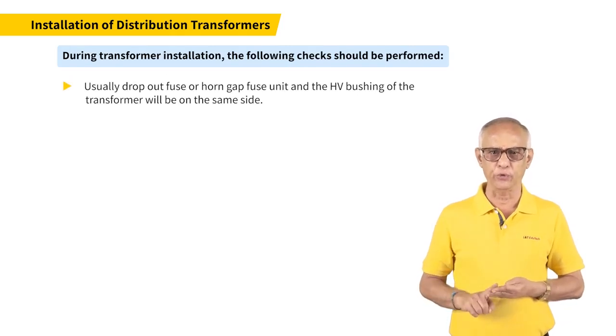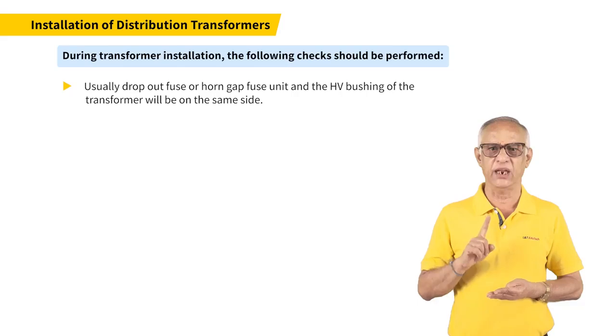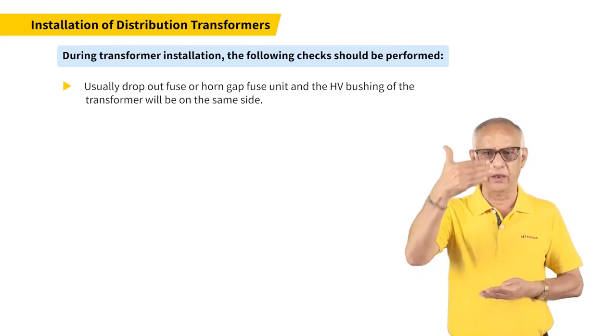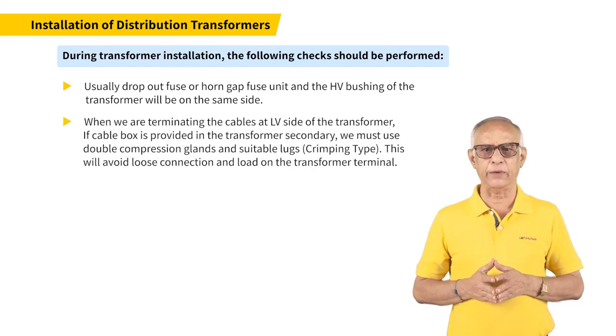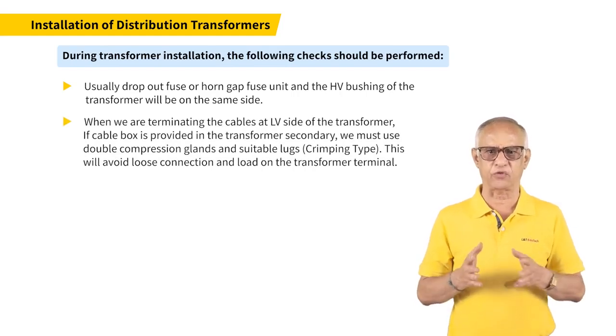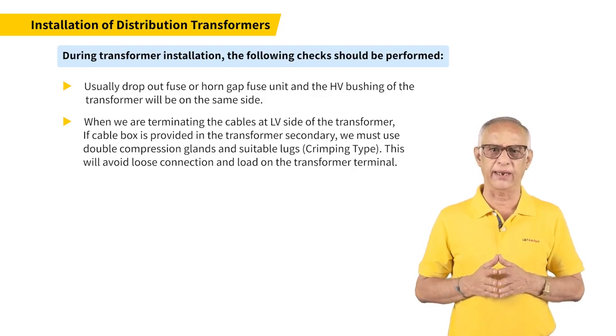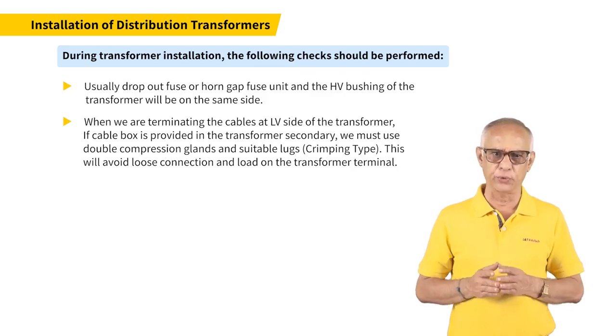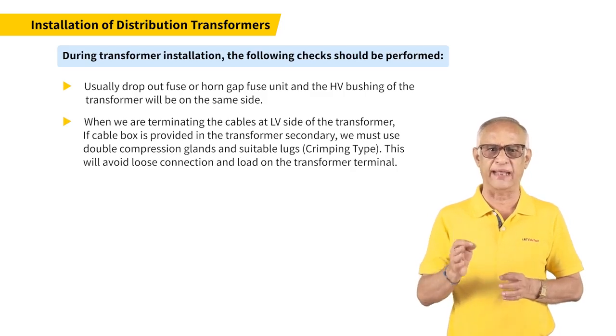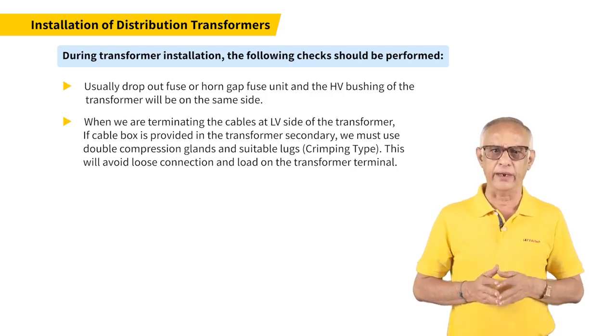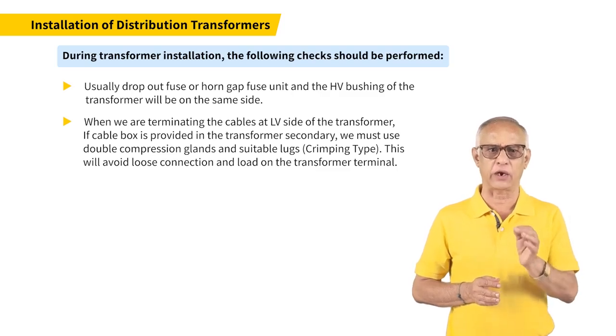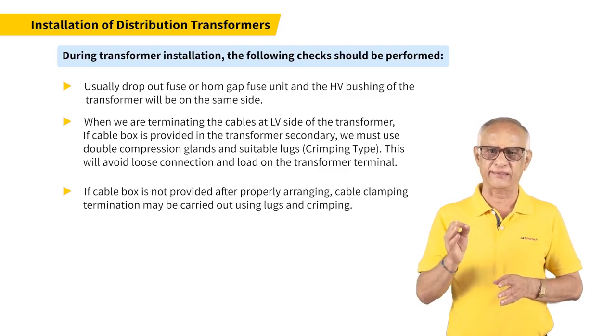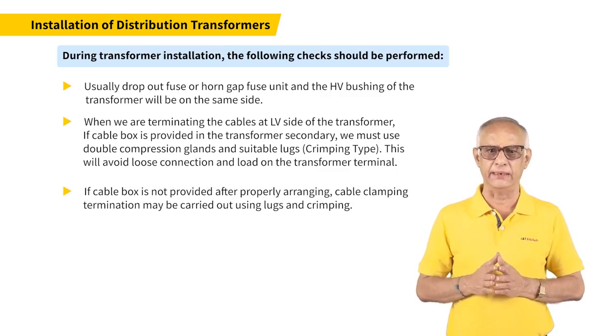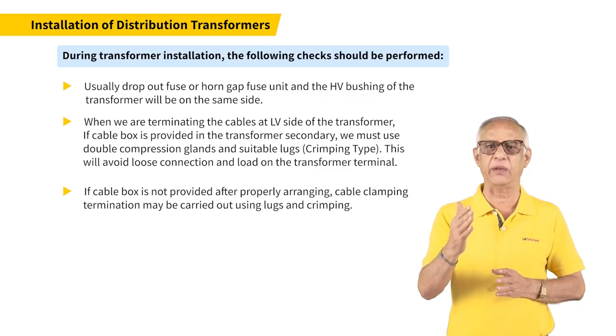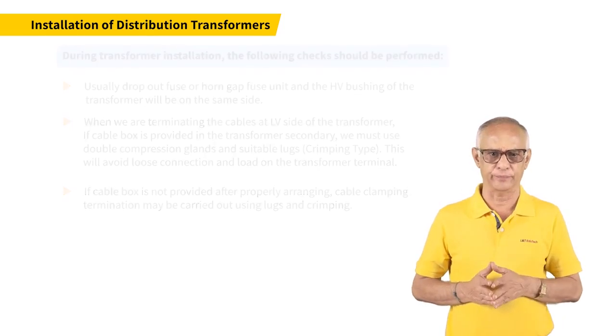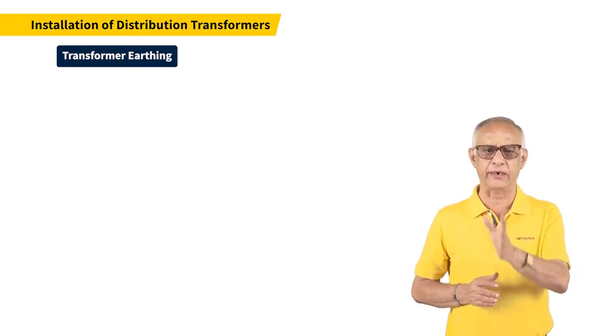Usually, the dropout fuse or horn gap fuse unit and the HV bushings of the transformer will be on the same side. When we are terminating the cables at the LV side of the transformer, if a cable box is provided in the transformer secondary, we must use double compression gland and suitable lugs of crimping type. This will avoid loose connection and load on the transformer terminal. If a cable box is not provided, after properly arranging cable clamping, termination may be carried out using lugs and crimping. Now let's learn about the transformer earthing.